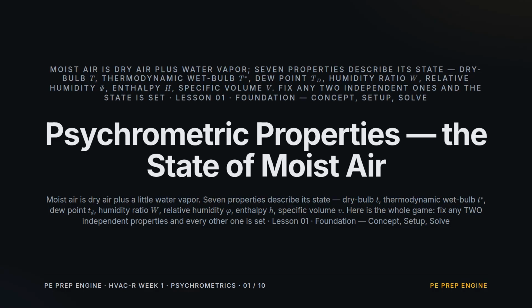HVAC Week 1, Lesson 1, Psychrometric Properties. Moist air is just dry air plus a little water vapor. 7 properties describe its state: dry bulb and wet bulb temperature, dew point, humidity ratio, relative humidity, enthalpy, and specific volume. Here's the whole game. Fix any 2 independent properties, and every other one is set.